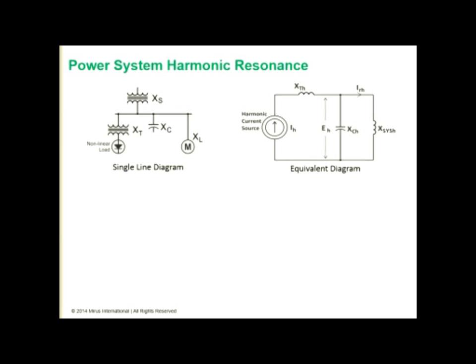Here we have the source and its reactance, so a simple one line that shows the source and its reactance. A nonlinear load, which might be a variable speed drive, fed from a transformer, and that transformer has a reactance component. And then power factor correction capacitors connected in parallel to the bus, and other loads on the system, which here we're representing as fixed speed motors or induction motors. The equivalent diagram of that simple one line is shown to the right.